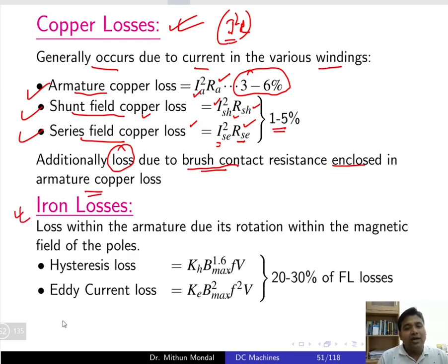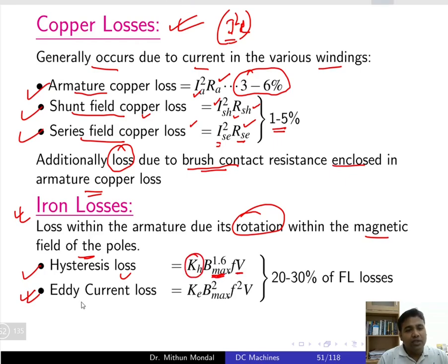The next loss is iron loss. Iron loss in the armature is due to the rotation of the core material in the magnetic field of the poles, comprising hysteresis loss and eddy current loss. Hysteresis loss is given as Kh × Bmax^1.6 × f × V, where Kh is the hysteresis constant. Eddy current loss is given as Ke × Bmax² × f² × V. If frequency, magnetic flux density, or volume increases, the iron loss increases. Iron loss constitutes 20 to 30 percent of the full load losses.